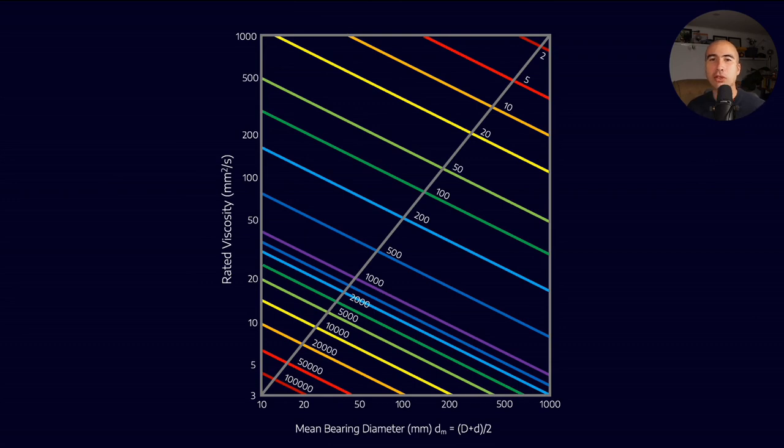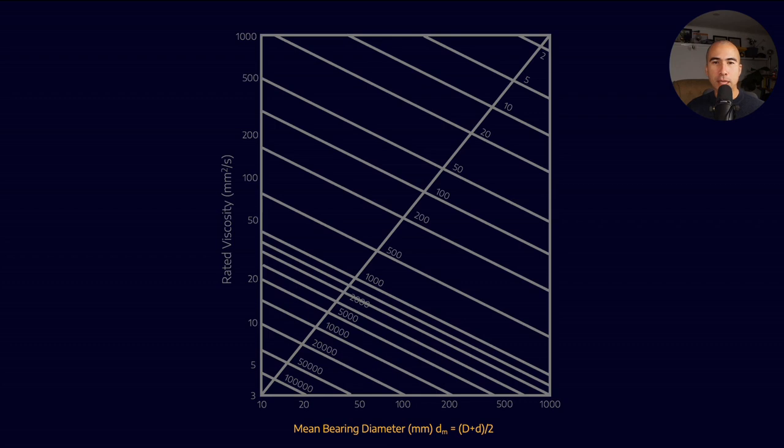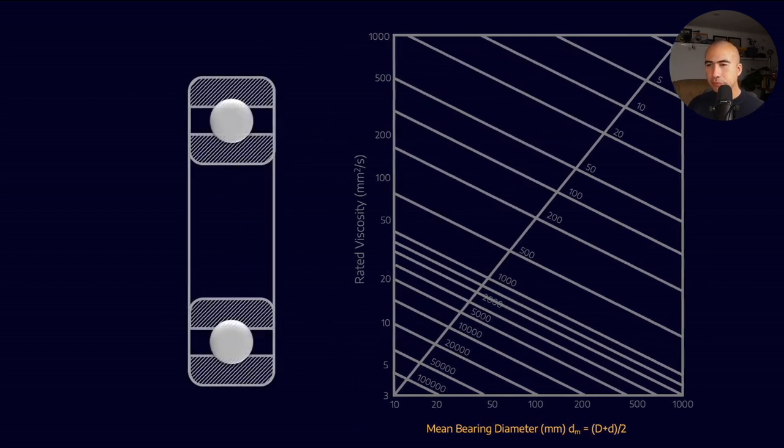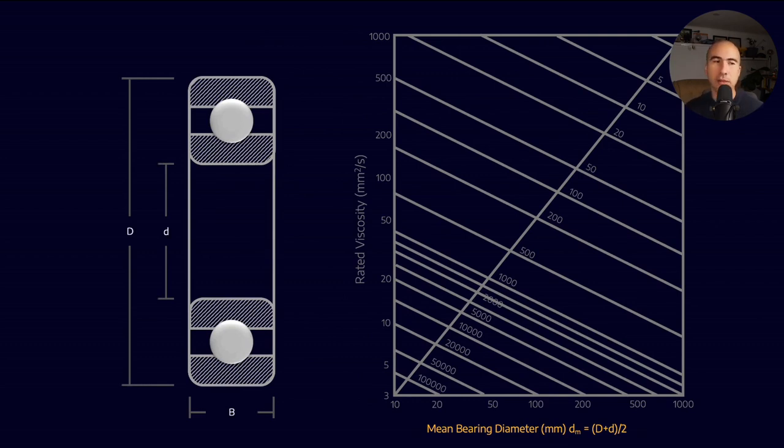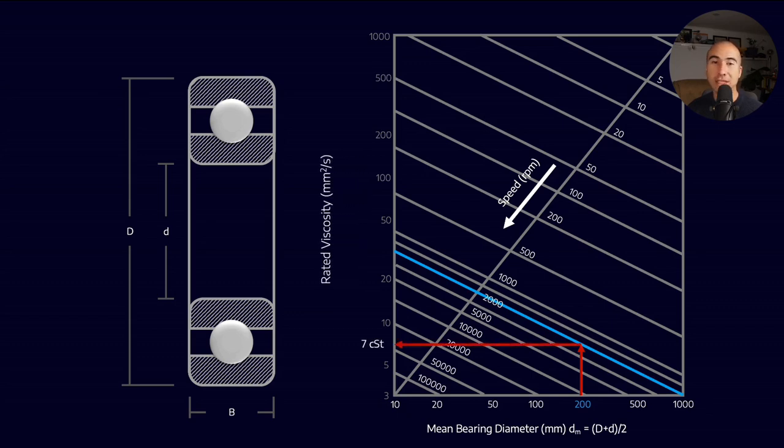More likely, you'll do calculations via a chart or app. This one from FAG shows mean bearing diameter and speed to get rated viscosity, with colored lines representing speed. The mean bearing diameter is outer diameter plus inner diameter divided by two. For example, with 200mm mean diameter at 2000 RPM, I go up to the 2000 line and read across for seven centistokes rated viscosity.